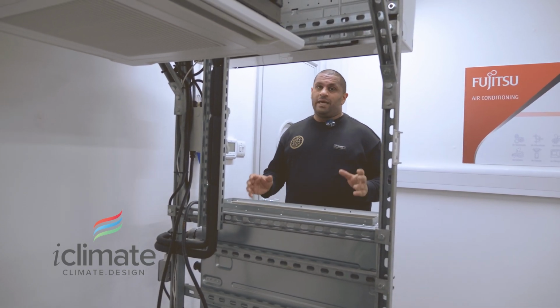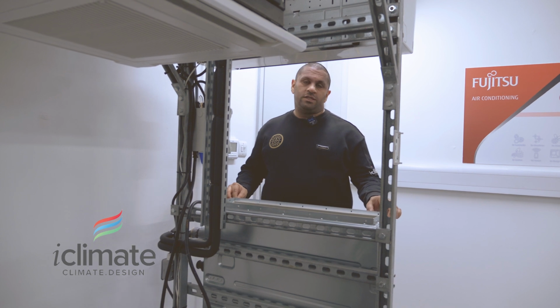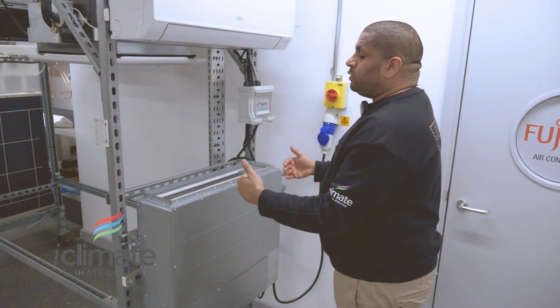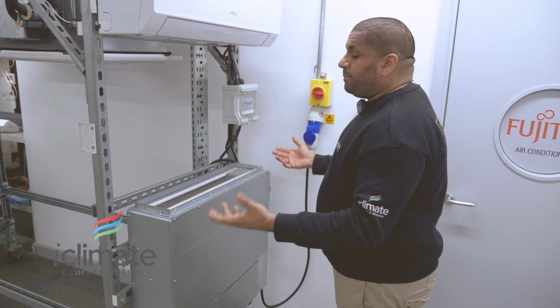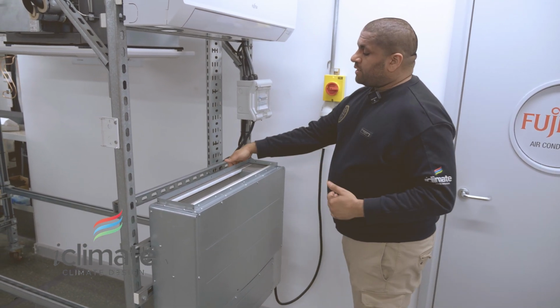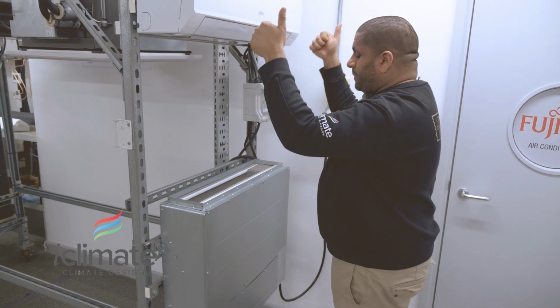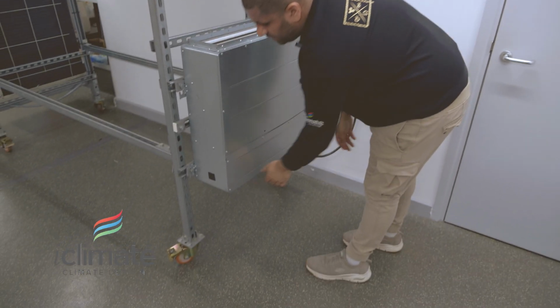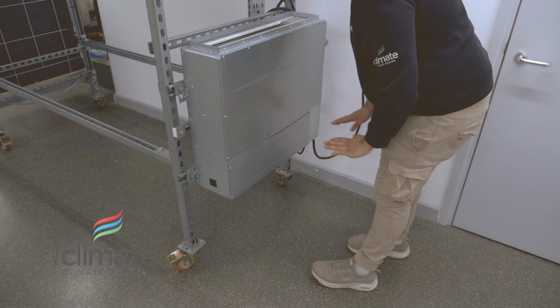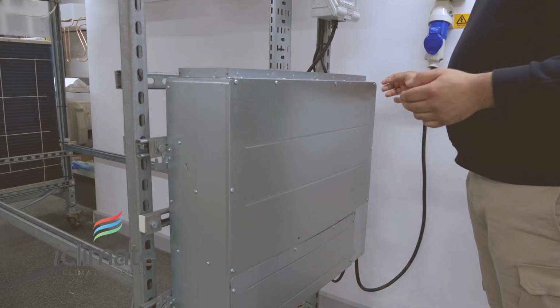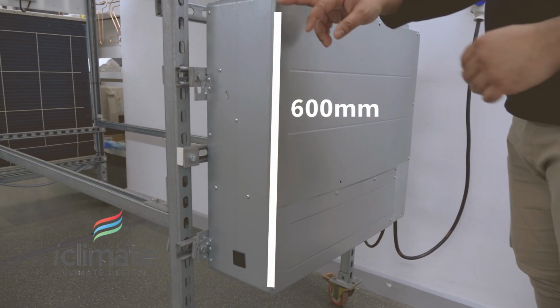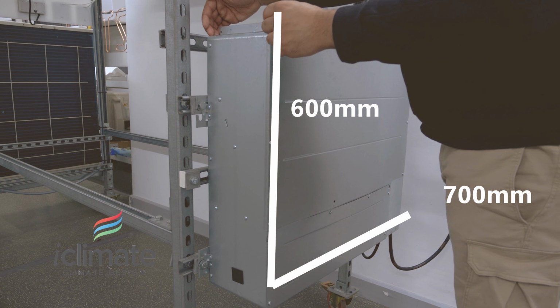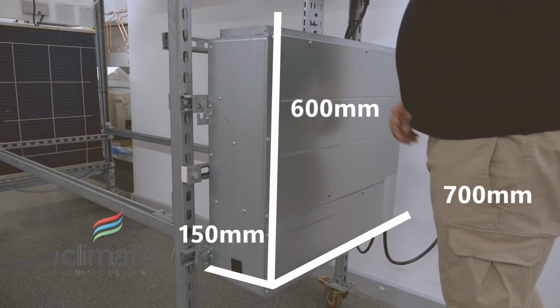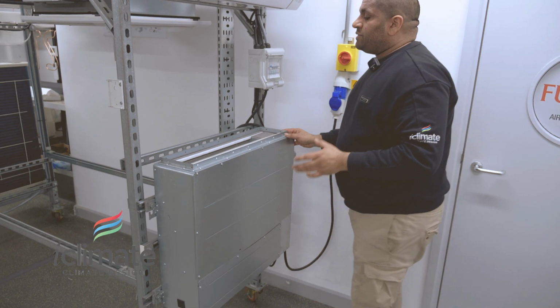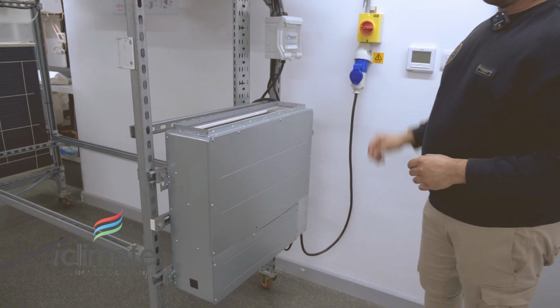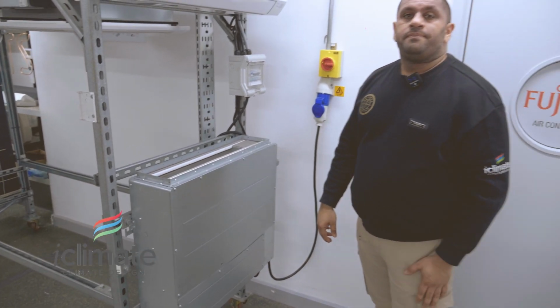Sticking with the concealed invisible air conditioning theme, the unit here now is a floor ducted unit, and it's designed to sit within a stud wall or a bulkhead wall that's been bought out, or a bookcase or custom joinery where this can be bolted onto the back wall. The air discharge for this is vertical at up, and the return air is taken from a configuration of under here, or this panel can be removed and adjusted so the return air can come back into the unit at this point. The footprint of this unit is quite compact. It is approximately 600 high, 700 wide, and 150 millimeters deep. It is ideal for a concealed installation and air discharge running at high level into the room if you don't have any ceiling space.